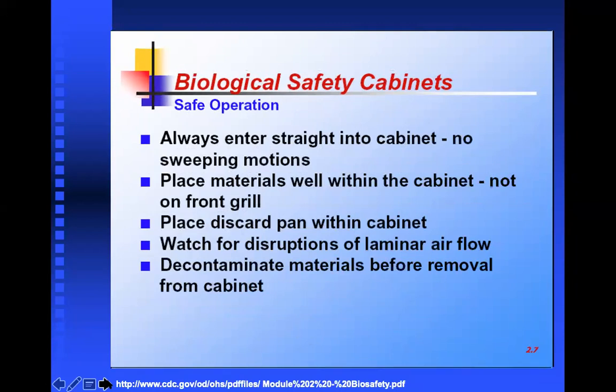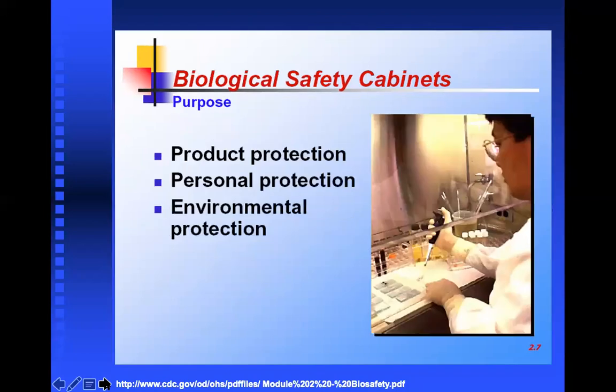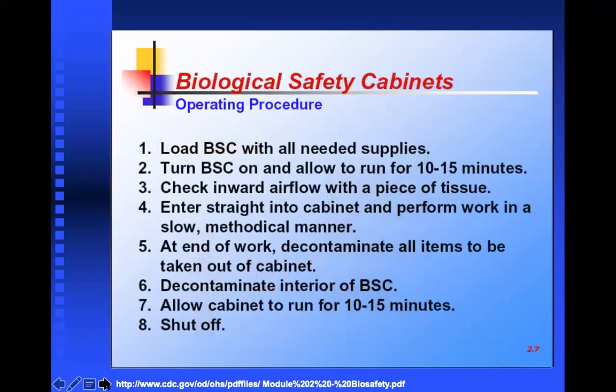Safe operation: always enter straight into the cabinet, no sweeping motion. Place materials well within the cabinet, not on the front grill. Place the discard pan within the cabinet. Watch for disruptions of laminar airflow. Decontaminate materials before removal from the cabinet. These are the important points. When you use it, you have to follow them.